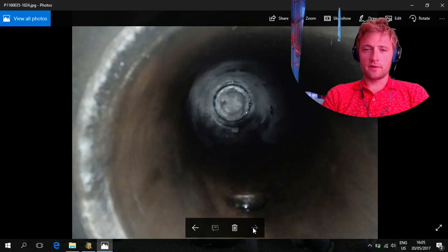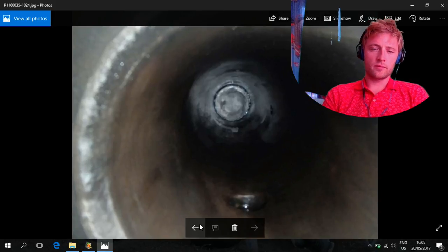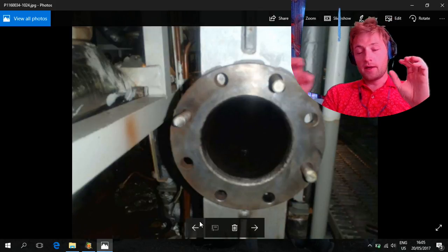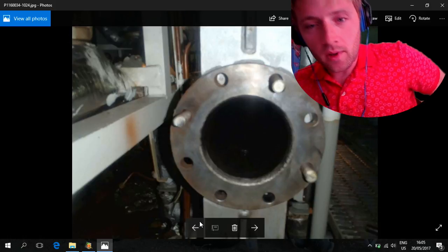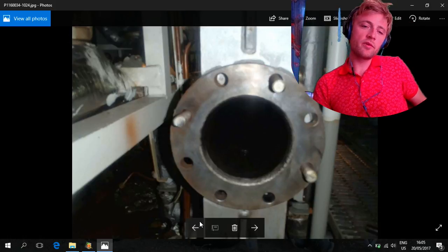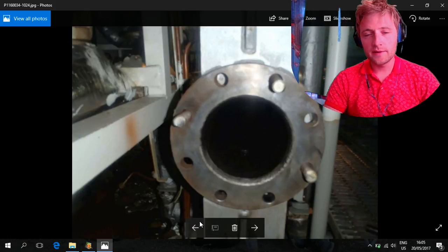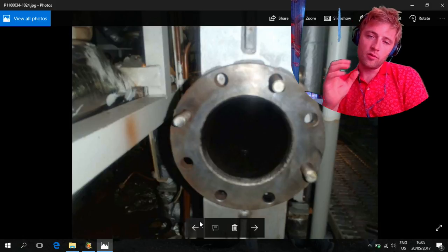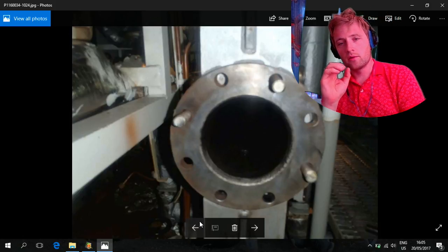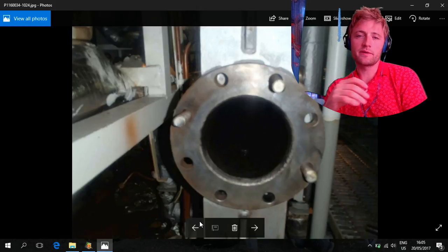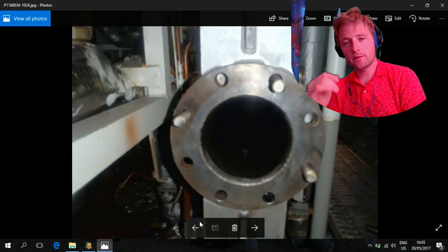This is the heater cleaned already inside, and now everything goes inside. Just remember, before you start your heater, open slowly the oil to pass inside to have a circulation of oil, and after that open the steam slowly.